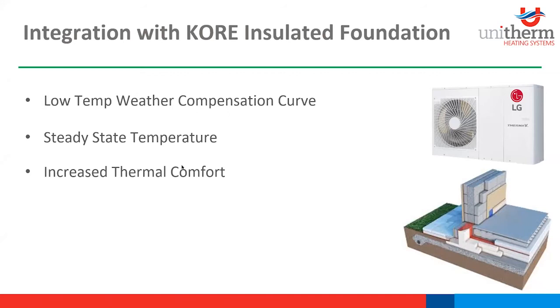So by running an inverter driven compressor in the heat pump continuously, the load is always very small and the LG Therma V doesn't have much work to do. So if it's just tipping away the whole time, keeping your leaving water temperature at 26, 28 degrees, we'll say, for an outdoor ambient temperature of 10 degrees, like today in the west of Ireland here, it's probably about 10, 11 degrees. So I don't know what it is over in the east there. It could be up at 16 degrees, but at 16 degrees we'd be looking at an even lower flow temperature of probably 27 degrees or 26. And that's still enough heat to heat the thermal mass and radiate off it. So that'll be left running continuously.